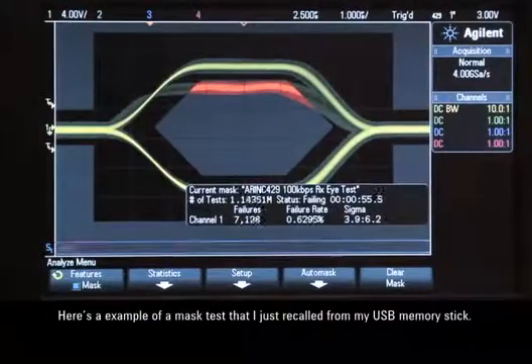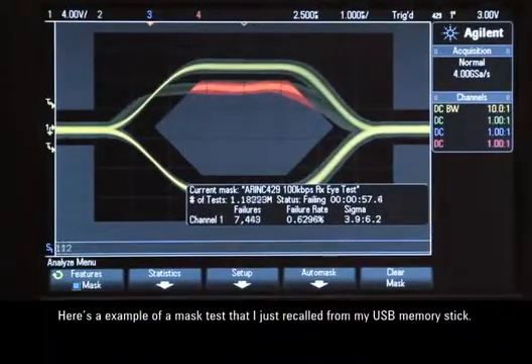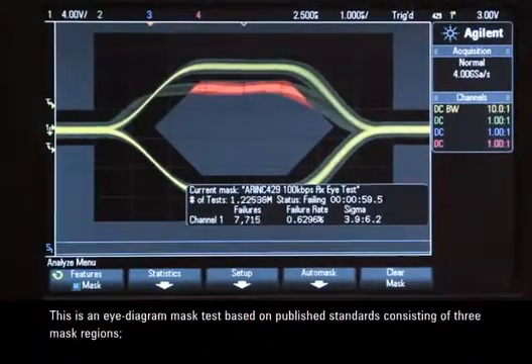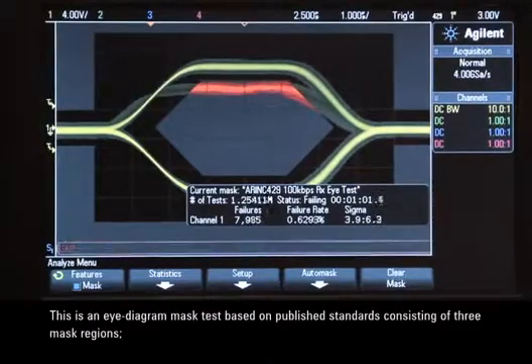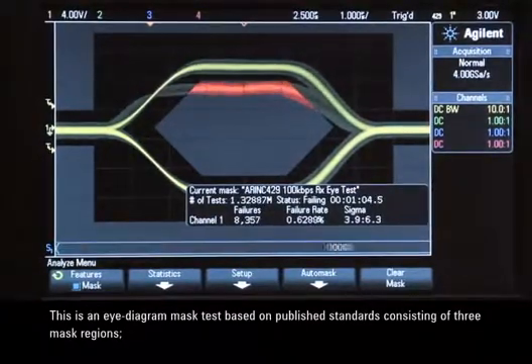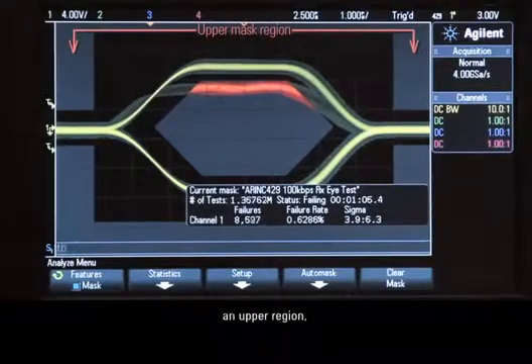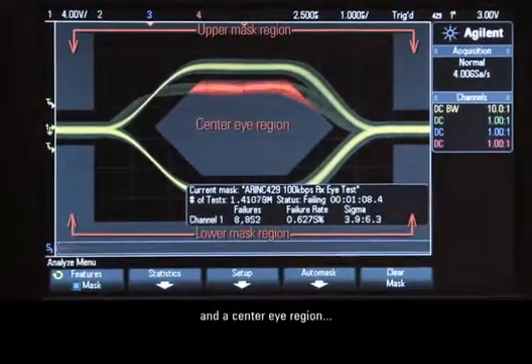Here's an example of a mask test that I just recalled from my USB memory stick. This is an eye diagram mask test based on published standards consisting of three mask regions, an upper region, lower region, and a center eye region.